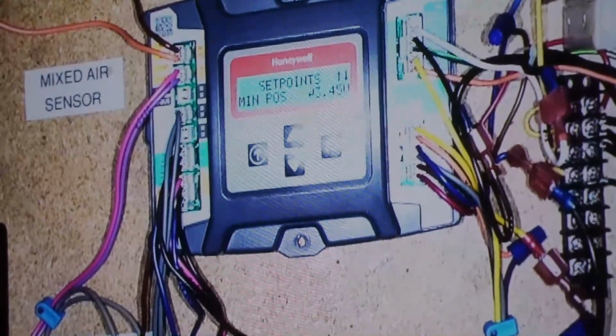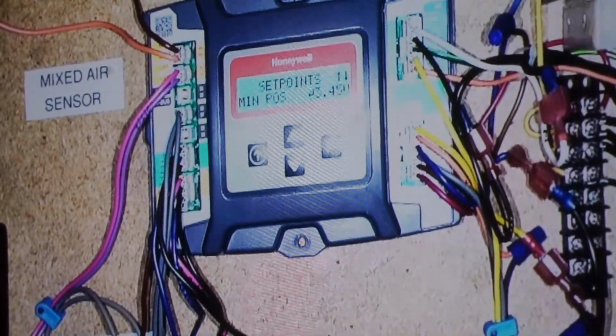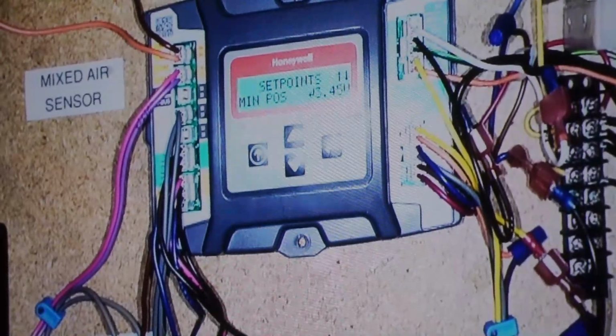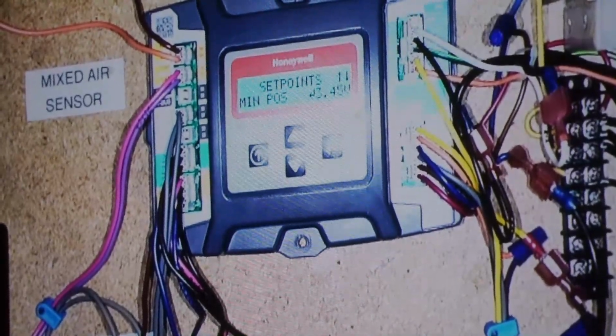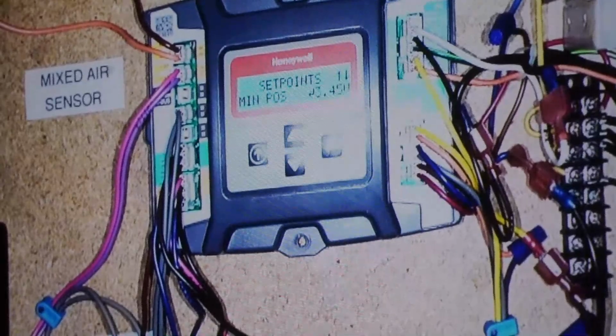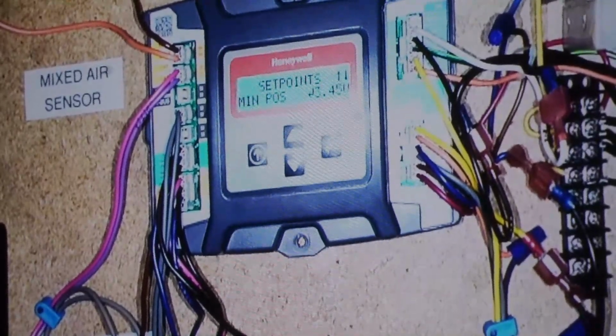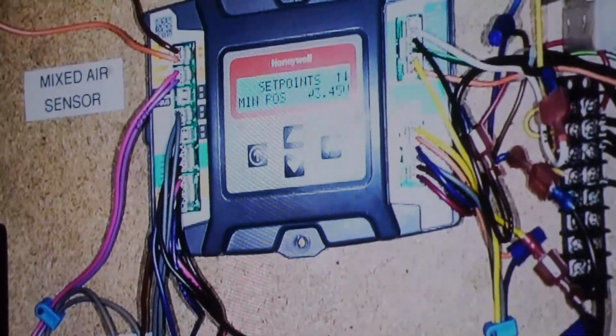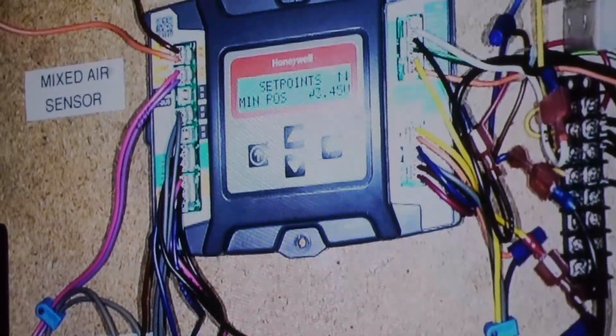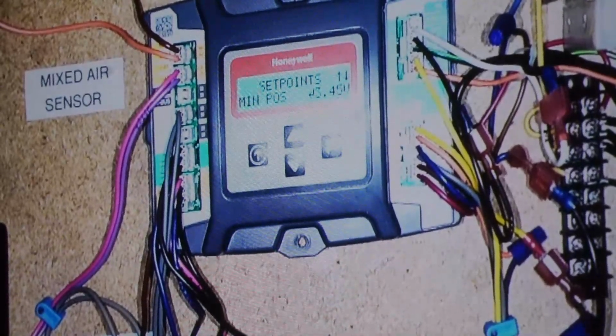Dampers aren't linear, so you're not going to see that curve that's a direct one-to-one relationship with movement. Go look at it. Go look at the damper. Look at your specs. Look at the building pressurization. Am I bringing in enough outside air? What was the setting right before this one that you just...